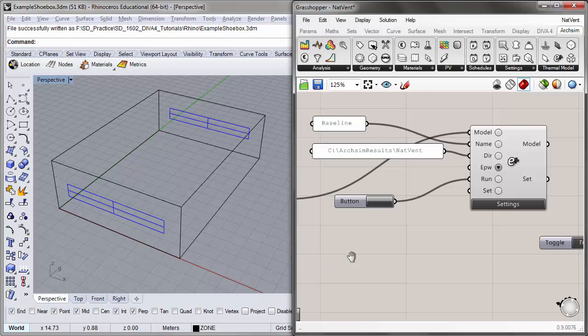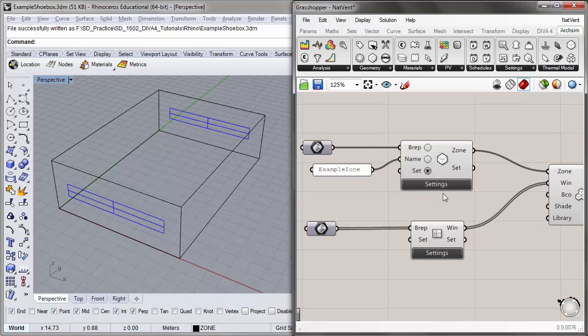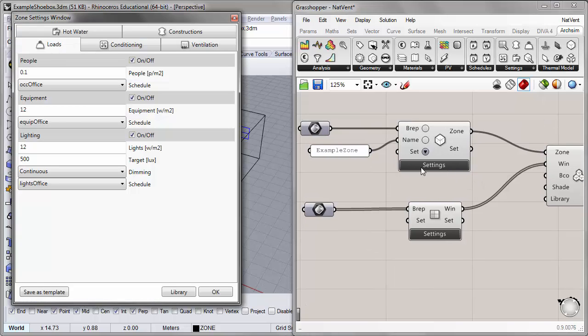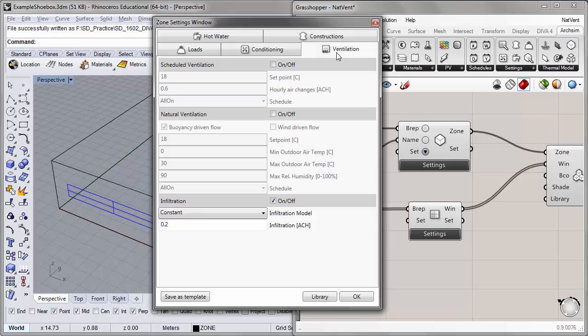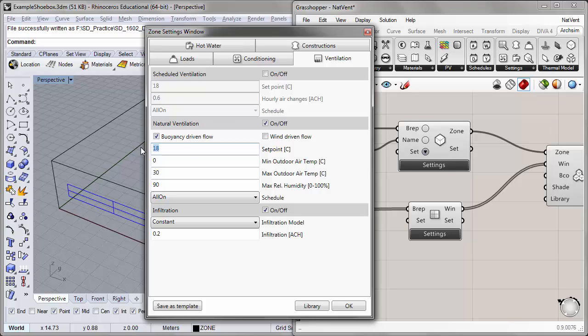Going back to Archsim, we can apply natural ventilation to our thermal zone by modifying the settings in the thermal zone component. I'll click on settings and under ventilation, we see a few different options. For this tutorial, we're going to be looking mainly at buoyancy-driven flow, which can be thought of as the stack effect — the flow that results from changes in density and temperature between inside and outside. We won't be looking at wind-driven flow for this tutorial. Here we can input a temperature set point; we'll leave the default 18 degrees Celsius.